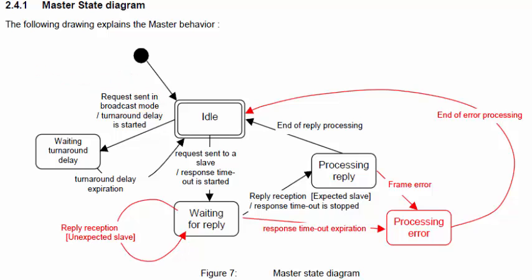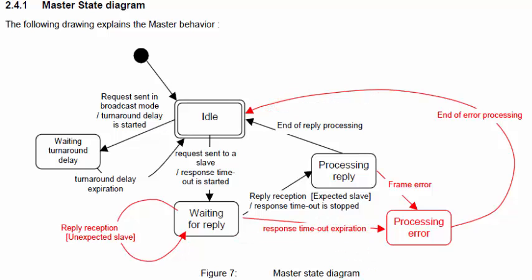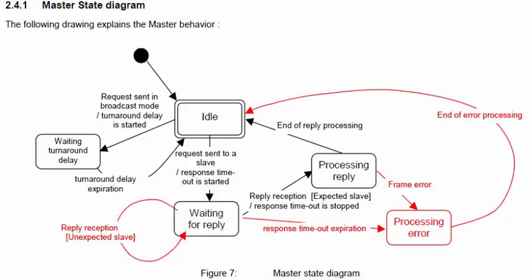If the master is sending a request to a particular slave, it initiates a different timer called the request/reply timeout. The master waits for the addressed slave to respond. If the slave doesn't respond within the reply timeout period, the master initiates an error and goes back to idle. But if the slave responds to the request, the master processes the reply and returns to idle. It's a pretty simple implementation of Modbus.